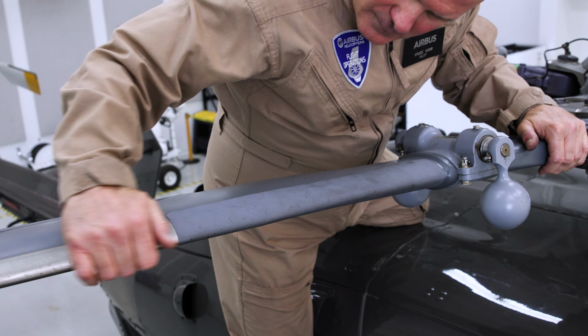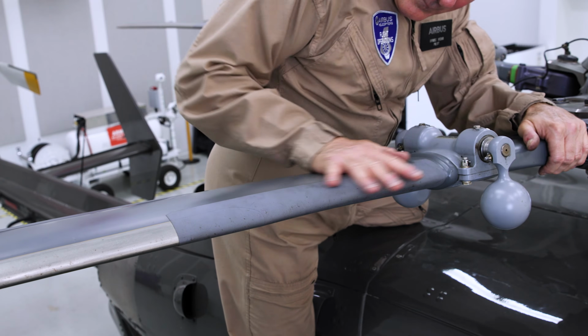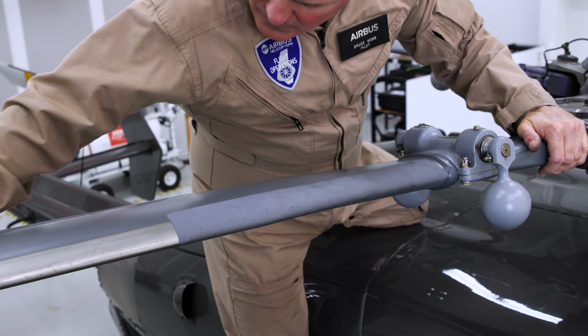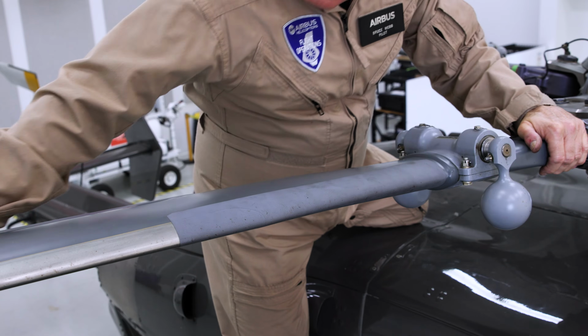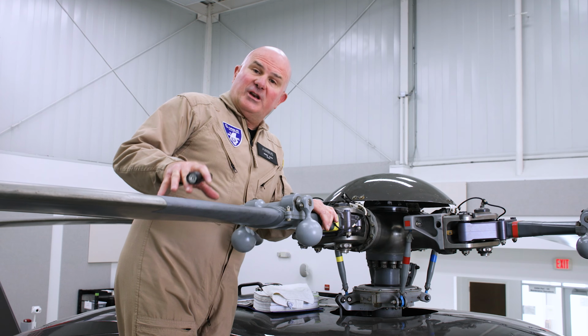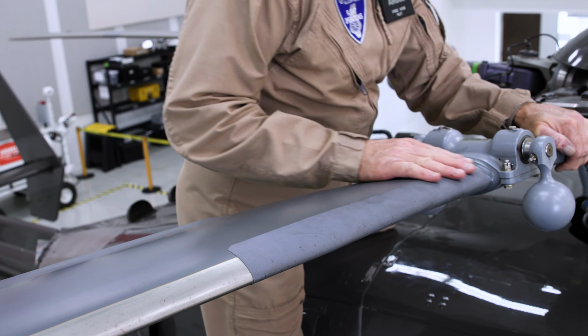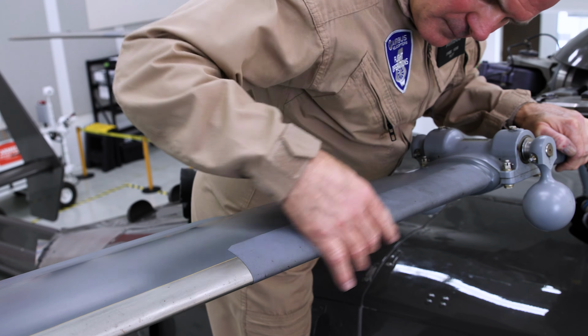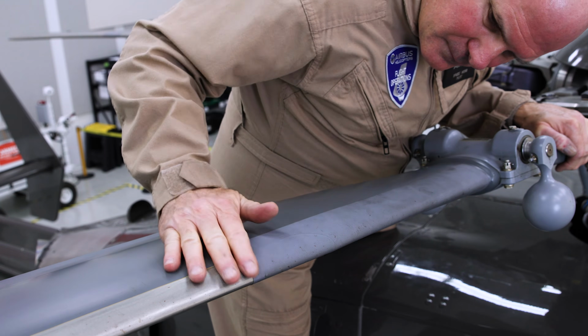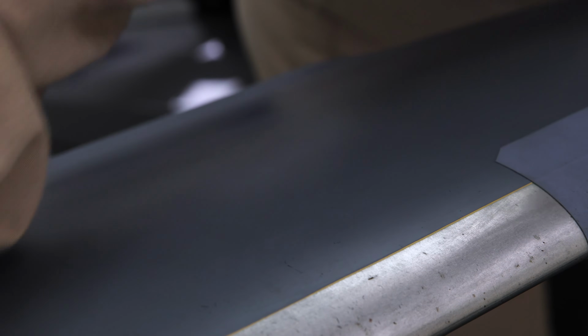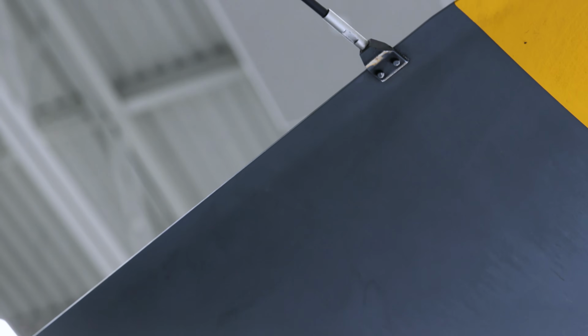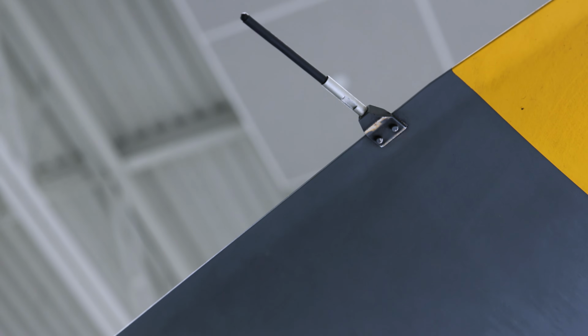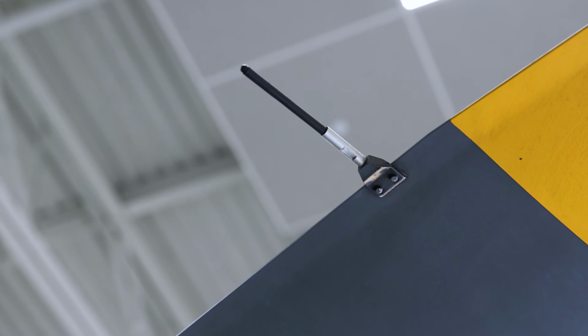The rotor blades themselves, of course we have 4. We want to look down the top of the blade, the bottom of the blade, the leading edge, the trailing edge to check for condition, no damage. Additionally, we'll look at the PU tape on the leading edge of each blade and the nickel erosion strip to make sure that it is correctly installed, undamaged. At the end of the blades, we'll check to ensure the trim tabs are in good condition and that the static wicks, 1 per blade, are in position as well.